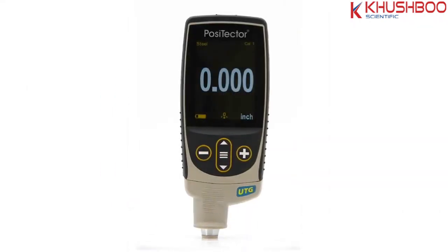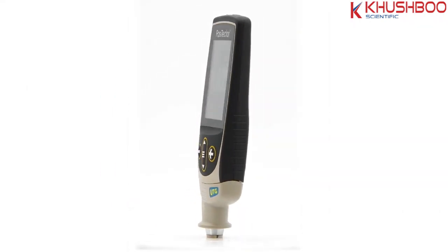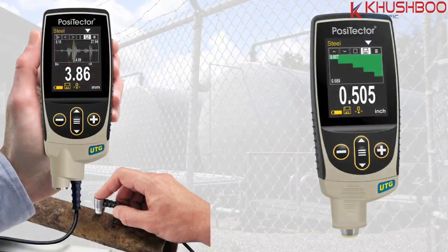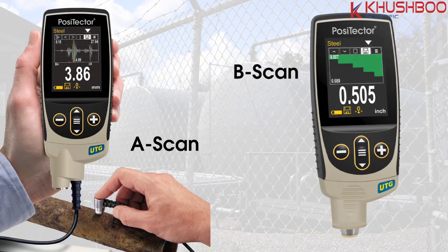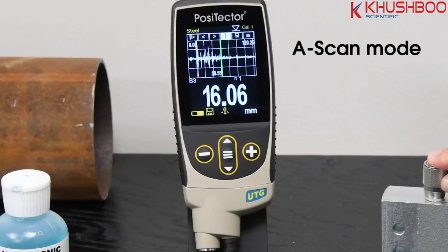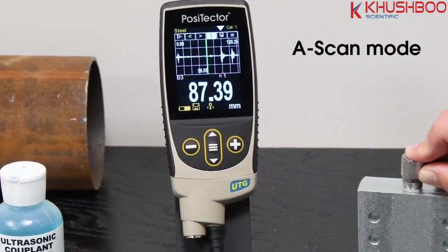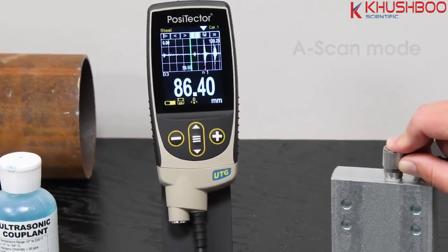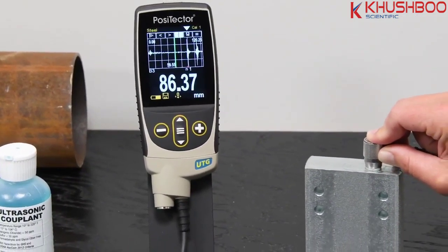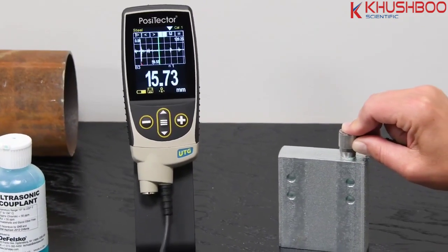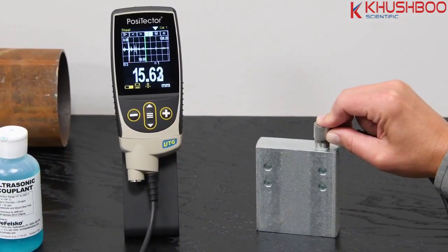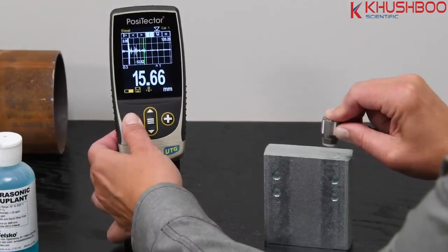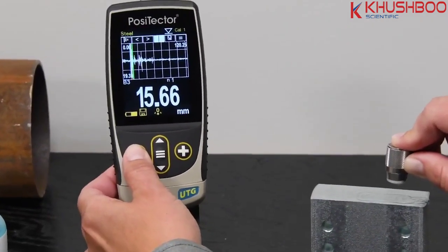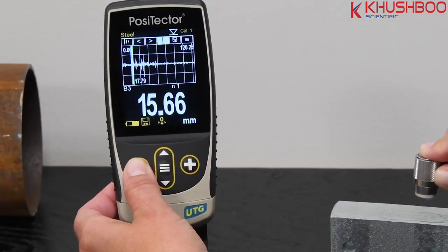When connected to a PosiTector advanced gauge body, PosiTector UTG probes gain A-scan and B-scan capability, features typically limited to much more expensive and complex instrumentation. A-scan mode displays the reflected ultrasound measured by the gauge, with the travel distance of the pulse on the x-axis and the strength or amplitude of the pulse on the y-axis. Using the built-in cursor, this powerful mode can be used to locate flaws and other features of the substrate.